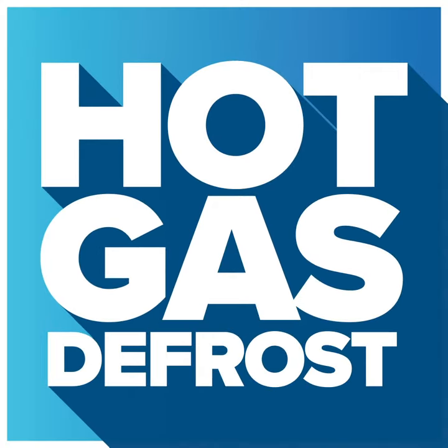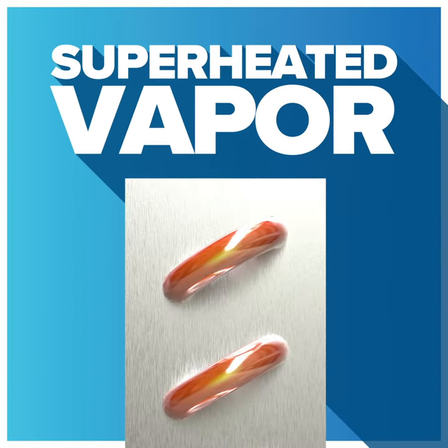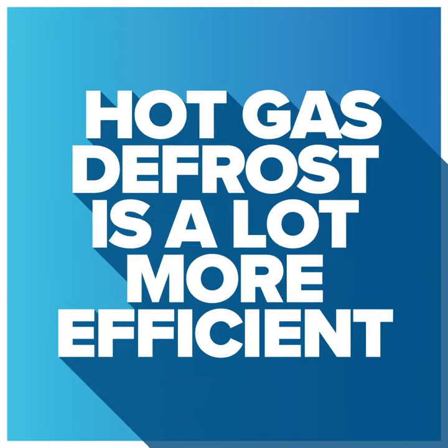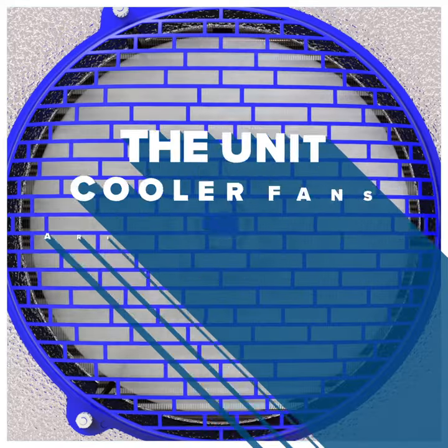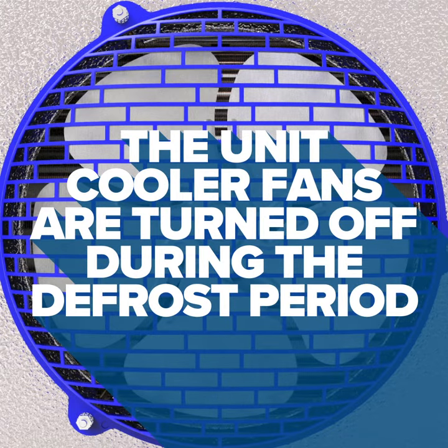Last is the hot gas defrost system, which uses the superheated vapor from the compressor discharge port to warm the evaporator coil to melt the ice. While not as widely applied as electric defrost, hot gas defrost is a lot more efficient since the heat source flows through the coil circuit, allowing more effective heat exchange with the formed ice. During this type of defrost, the evaporator fans are turned off for the defrost period.